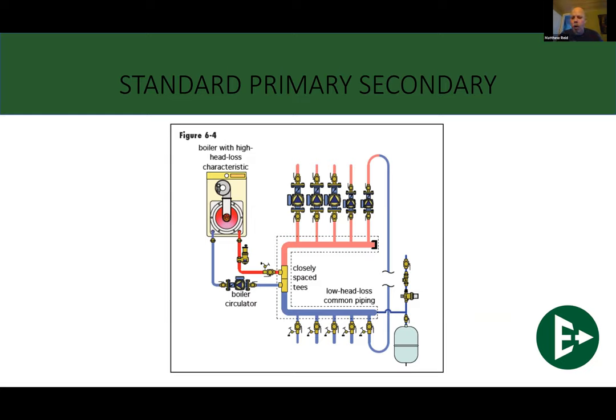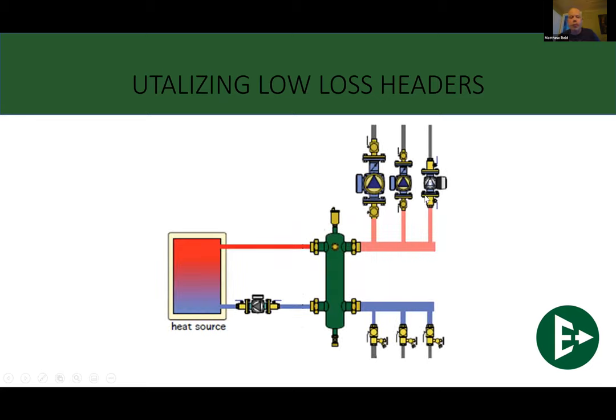And they work on a law of pressure flow through a set of closely spaced tees: what goes in must come out. The way that they operate is just like that. So as you are moving water into that loop, the exact same amount of water is leaving that loop. So that's going to limit the amount of pushback that you can get from any of the pumps, because this will create its own individual circuit by doing primary secondary. But preferably, that leads us into low loss headers.